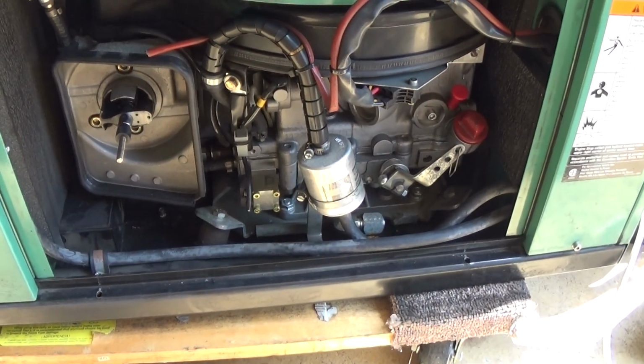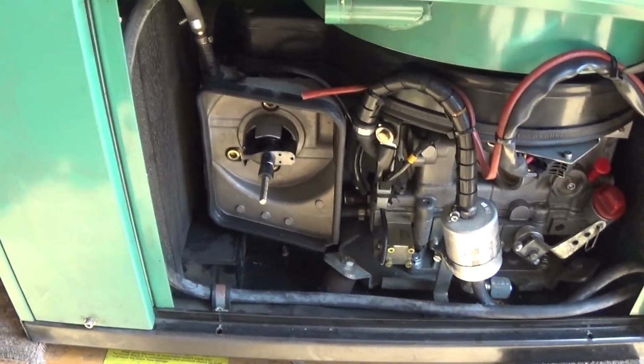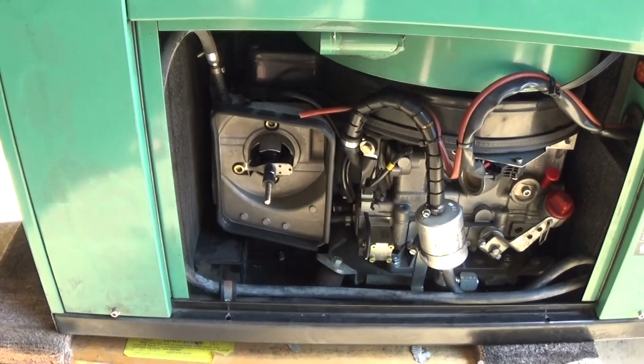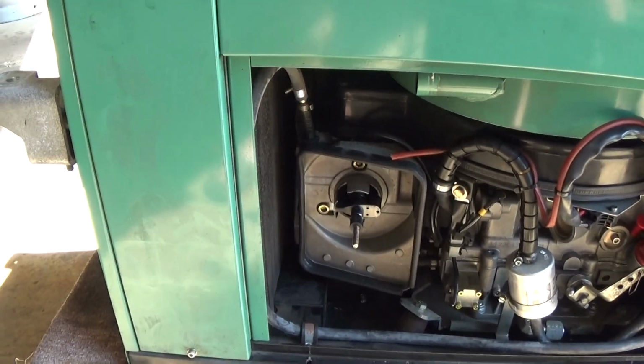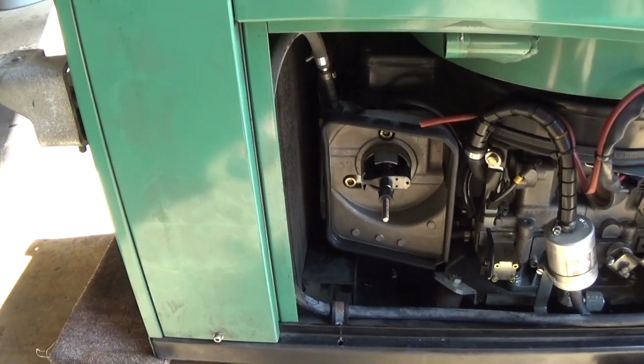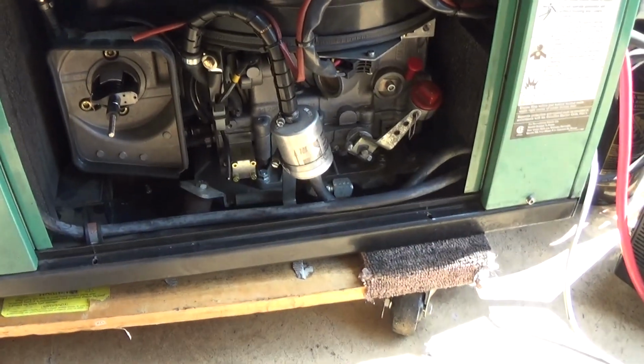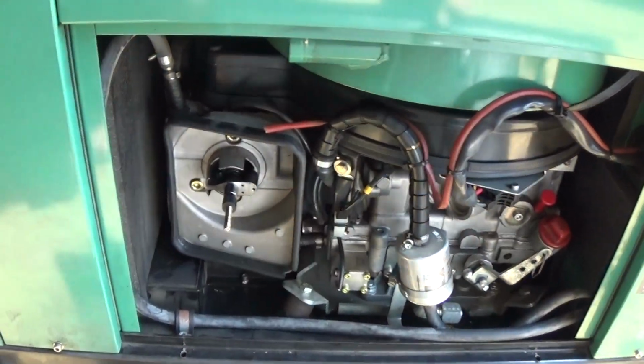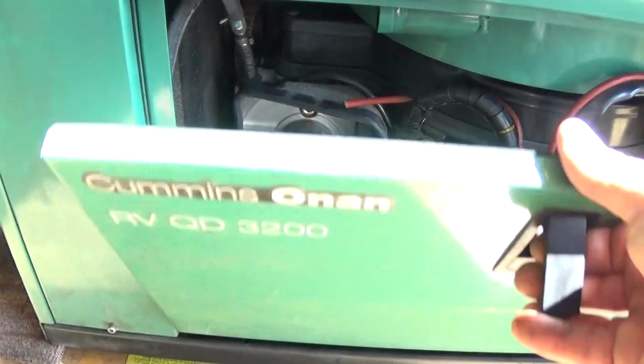Replace that fuel filter too—I forgot to mention that. Air filter, fuel filter, change the oil again, put a new gasket on the valve cover, and yeah, another load bank, and we'll try to bring it up to 100%. See if she'll do it.